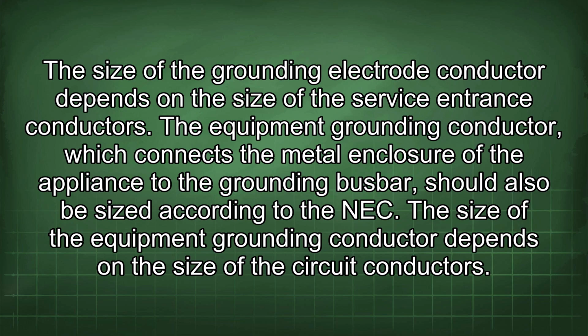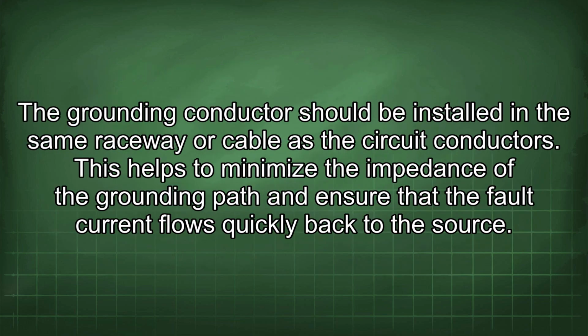The equipment grounding conductor, which connects the metal enclosure of the appliance to the grounding busbar, should also be sized according to the NEC. The size of the equipment grounding conductor depends on the size of the circuit conductors. The grounding conductor should be installed in the same raceway or cable as the circuit conductors. This helps to minimize the impedance of the grounding path and ensure that the fault current flows quickly back to the source.